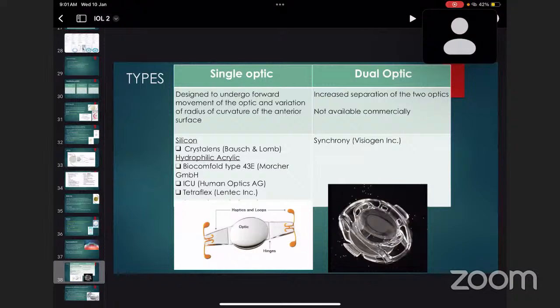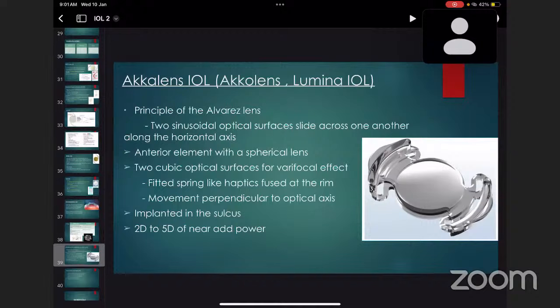In dual optic, it's increased separation of the two optics, not available commercially. Example is Synchrony as shown in the image. Then there's Akkalens intraocular lens, accommodative intraocular lens known as Akkolens or Lumina IOL. It's based on the principle of the Alvarez lens in which two sinusoidal optical surfaces slide across one another along the horizontal axis. Anterior element with spherical lens and two cubic optical surfaces for varifocal effect. They are fitted with spring-like haptics fused at the rim and movement perpendicular to optical axis. These are implanted in the sulcus with two diopter to five diopter of near-add power.